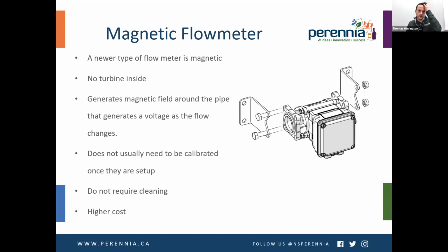The newer type of flow meter that we're seeing on the market now is a magnetic flow meter. If you look through it, there are no moving parts inside. The way it works is it generates a magnetic field around your pipe or your boom, and it generates a voltage that changes as the flow changes through it. Some of the advantages are they generally don't need to be calibrated once they're set up, and they don't really require much cleaning other than making sure there's no accumulation inside the plumbing. But the main downside is they're definitely at a higher cost than the regular flow meter.